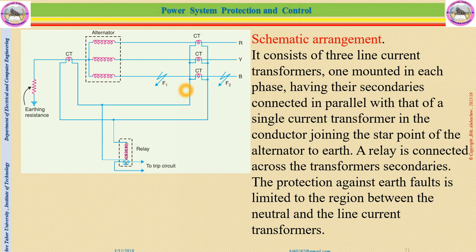The schematic arrangement consists of three line current transformers, one mounted in each phase, with the secondaries connected in parallel, and a second current transformer in the conductor connecting the star point of the alternator to earth. A relay is connected across the transformer secondaries. The protection against earth fault is limited to the region between the neutral and the line current transformers. You can see the line current transformers here.